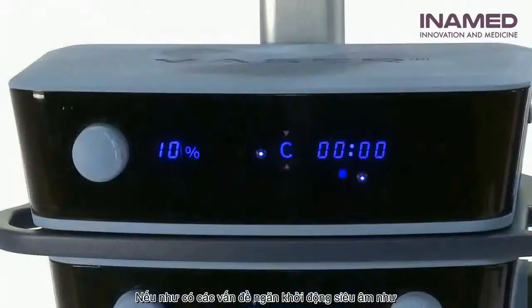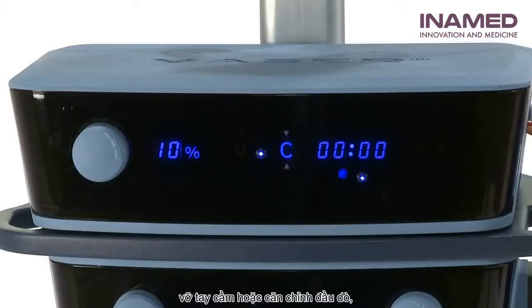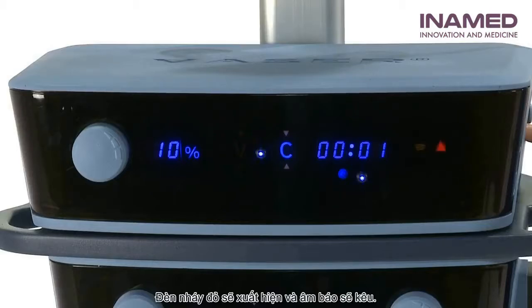If something is preventing ultrasound activation, such as a broken handpiece or torquing the probe, the Vaser amplifier will automatically fault for safety. A flashing red triangle will appear on the display and an alarm will sound. For this or other troubleshooting issues, check the quick guide or review the user guide. You can also contact Sound Surgical Technical Support at the number printed on the system.